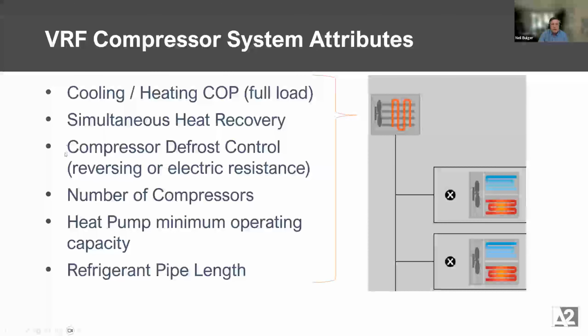A lot of information can be defined and needs to be thought about for defrost. Does the unit reverse its compressor? Does it do that and have some electric resistance component? Does it do one or the other? The number of compressors in the box, a lot of these systems come in modules and you open that up and it's just made of smaller modules. So a 20-ton unit is just 4 5-ton units.